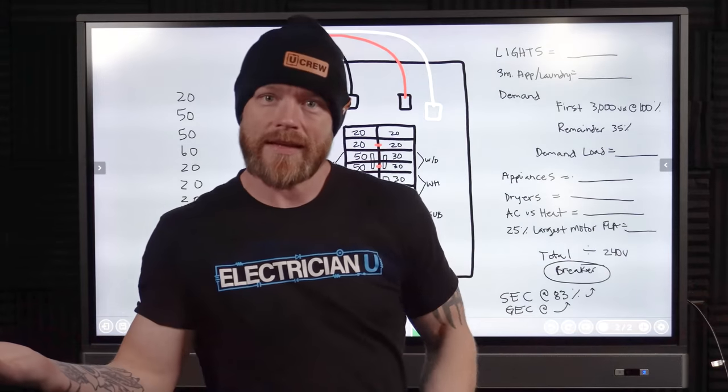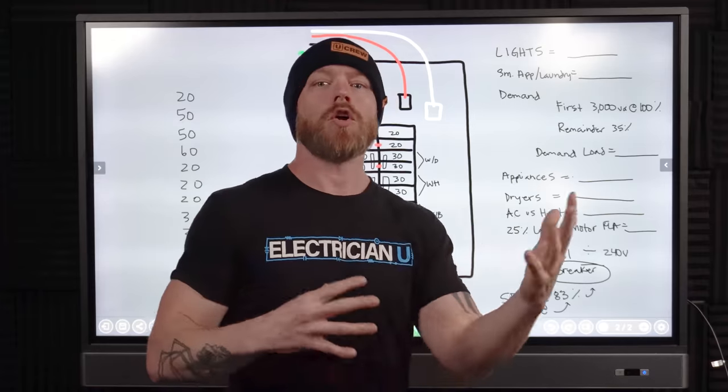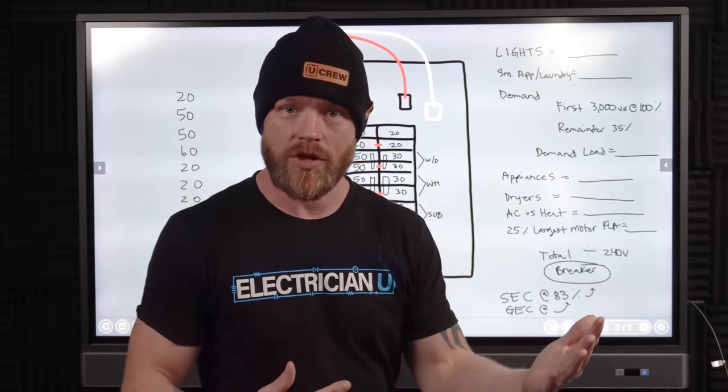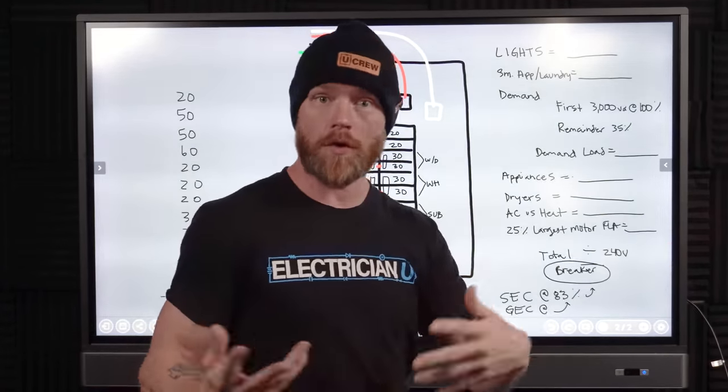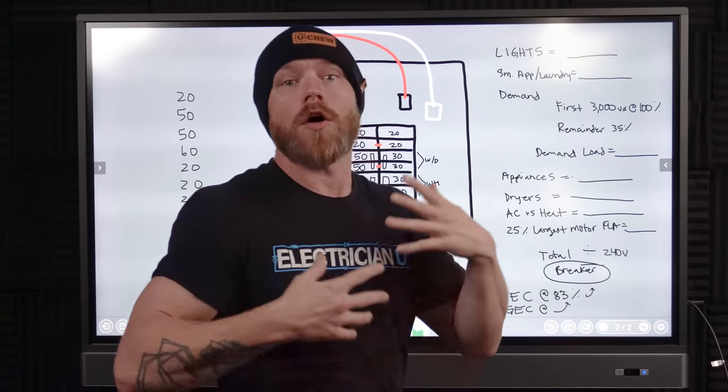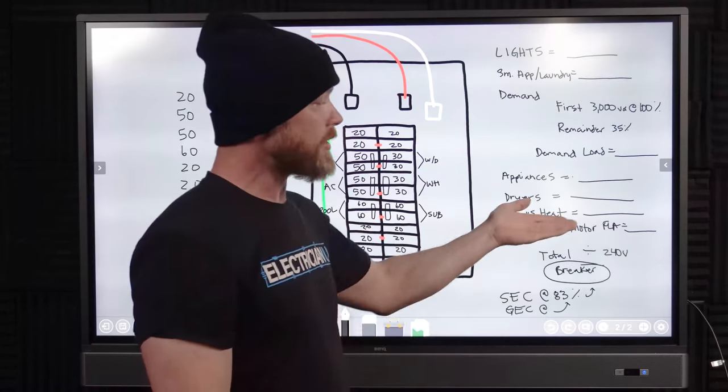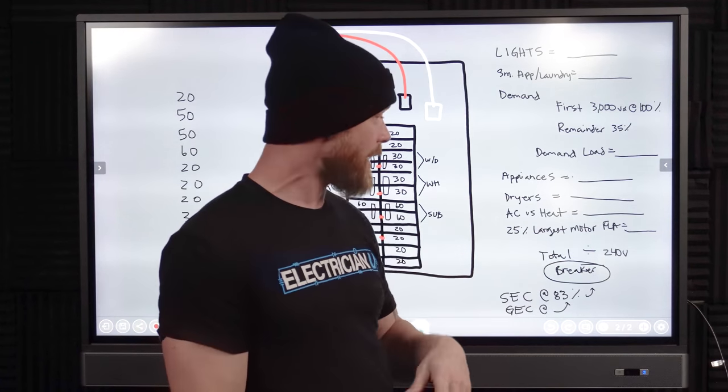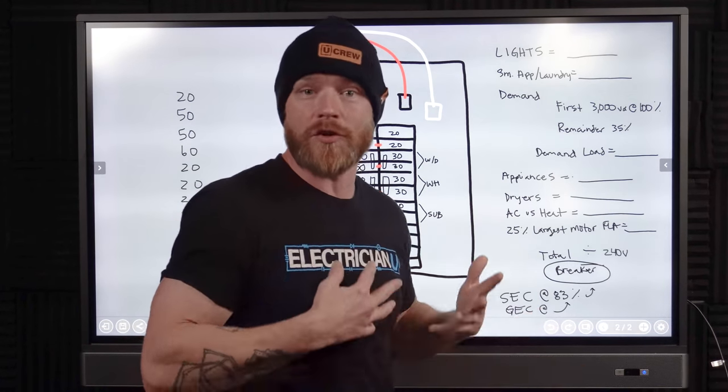AC versus heat. Well, you're never running AC and heat at the same time. So you have these kind of non-coincident loads where you have like things that aren't going to really interact with each other. So you usually take the bigger one, whichever is higher, your heat or your AC. Then we have largest motor FLA. So if you have other motors in your house, for some reason, you've got other kind of crazy things. We allow like a percentage of the nameplate rating of that motor to be added to its own line.